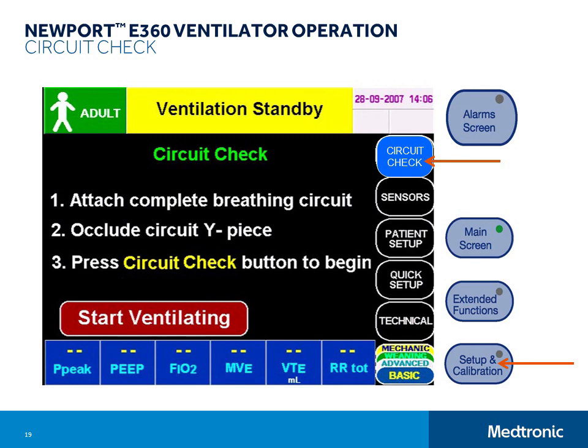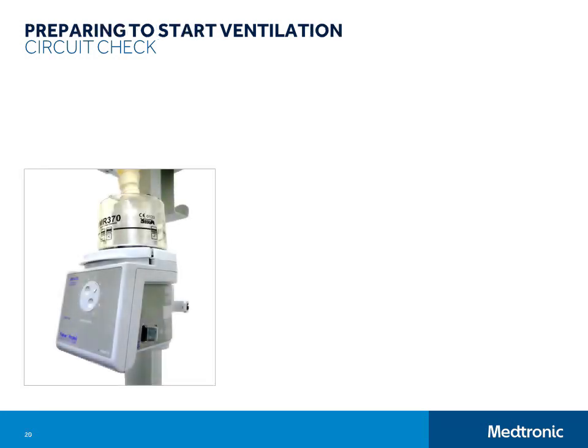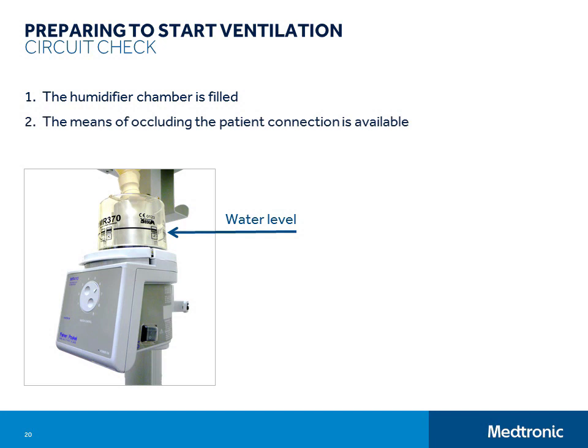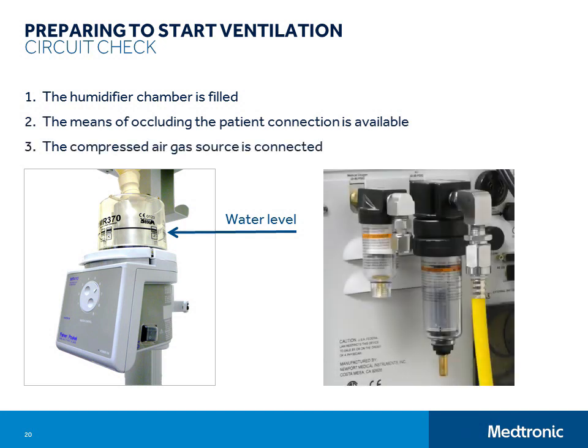When the ventilator is powered on, it automatically goes to the circuit check screen. But if you navigate away from that screen while in the standby condition and need to get back to it, simply push the Setup and Calibration button on the panel and then touch the Circuit Check button. Before you start the circuit check, take a moment to make sure that the humidifier chamber is filled to an appropriate level and that you have a means of occluding the patient connection of the circuit. And make sure that the compressed air gas source is connected and turned on. Failing to connect a compressed air gas source will cause the circuit check to fail.